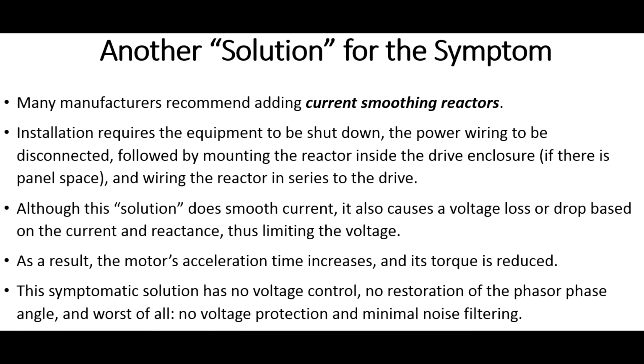In many facilities, many manufacturers actually recommend adding line reactors ahead of a drive and/or chokes after a drive. The chokes are there for smoothing the spindle speed, typically in a system where you would have a tool changer, and it prevents the motor from cogging, or not turning very smoothly at low speed. The line reactors are there to try to smooth the current. They don't do much for voltage, because an inductor, which is what a line reactor is, actually resists a change in current. So the change in current isn't as rapid as it would be if you just had the power feeding directly into the drive.